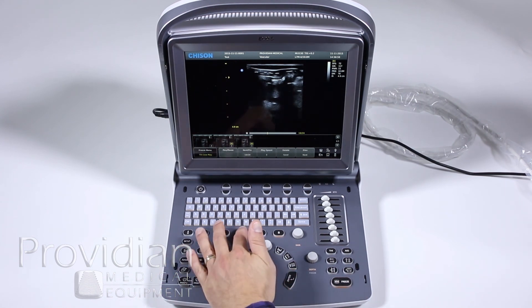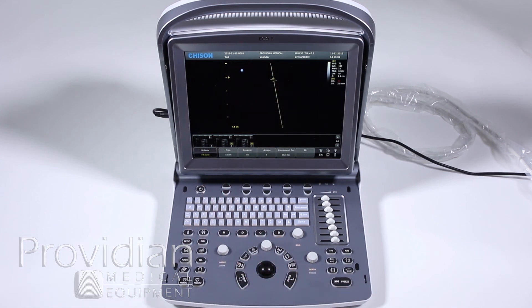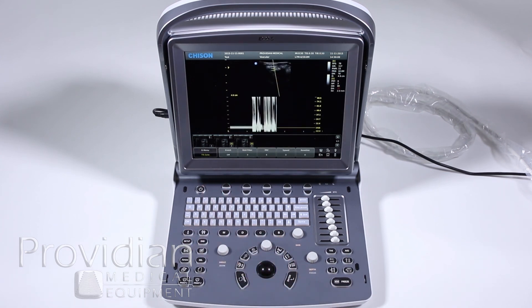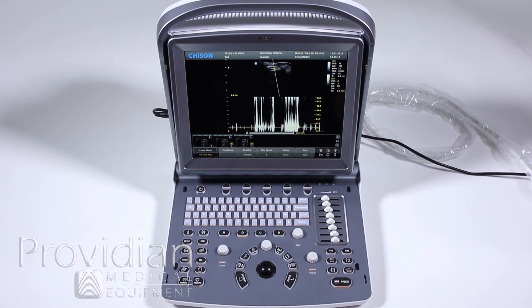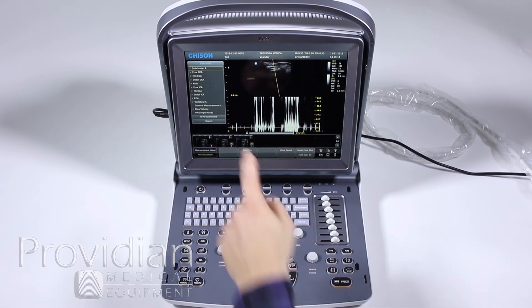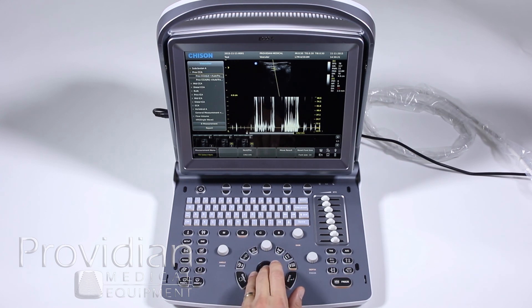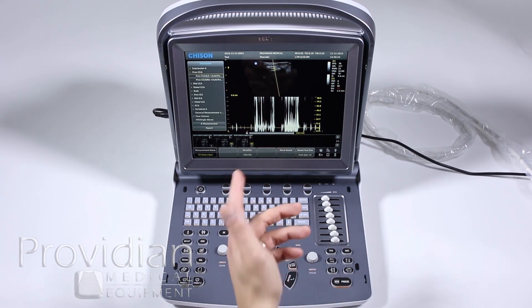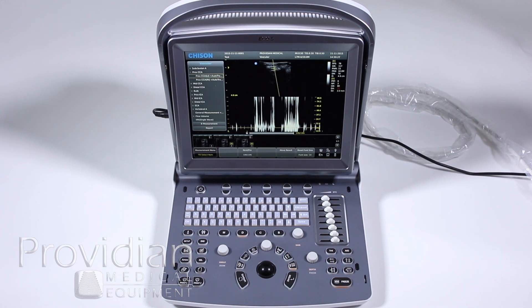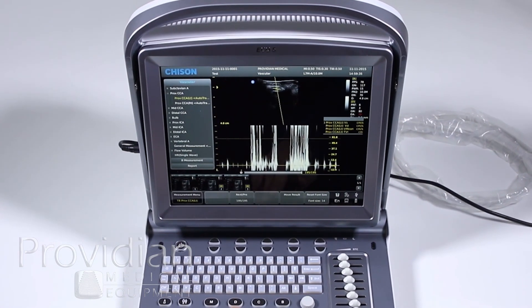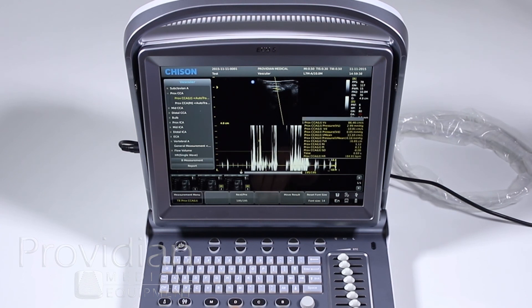It's very similar for Doppler calculations — hit Doppler, then hit calc. It shows all your vascular calculations and you can choose whatever you want. There are also auto trace functions in there. This is just for demonstration so we're not getting a real Doppler signal, but any measurement you make here will go to the report. With this auto calc, I'm choosing my starting and endpoint, and the auto trace follows along with all these numbers, which will appear on my report.